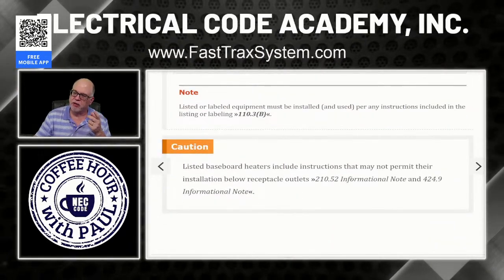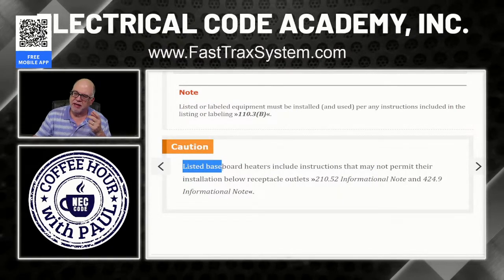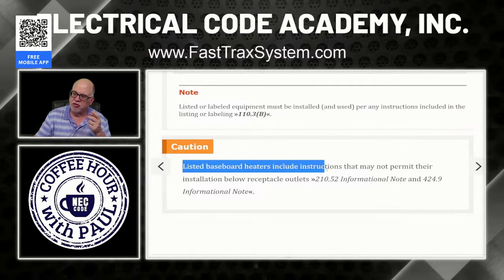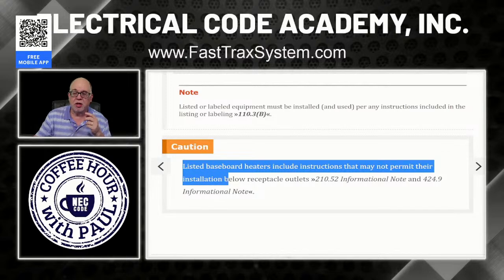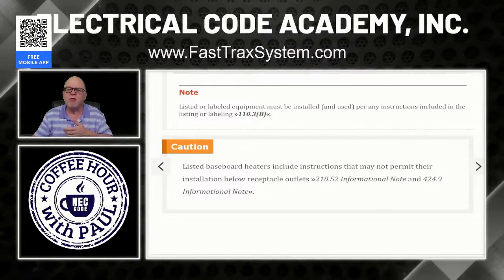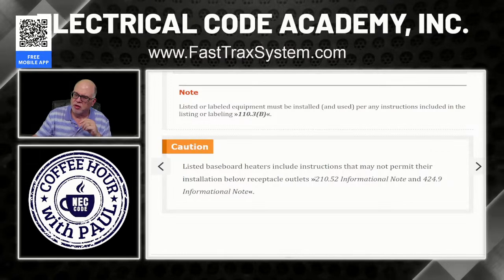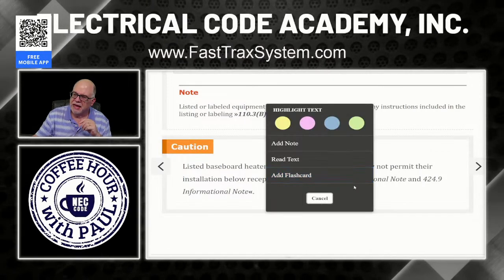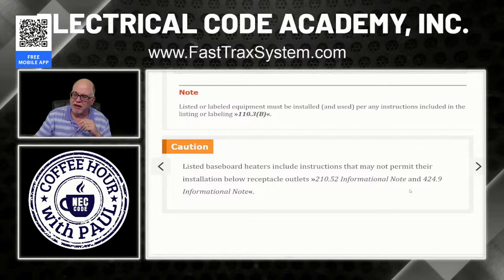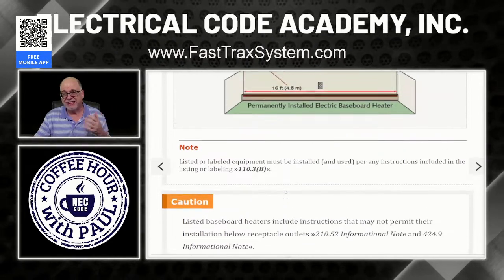Now, here's the informational note, folks. It reminds us, listed baseboard heaters including instructions may not permit their installation below a receptacle outlet, okay? And where does it say that? Where does it remind you of that? So you have to go look at what the manufacturers say. That is an informational note under 210.52, and it's also reiterated under 424.9 in an informational note to do that. If the manufacturer doesn't say there's a problem with it, then you could do it.